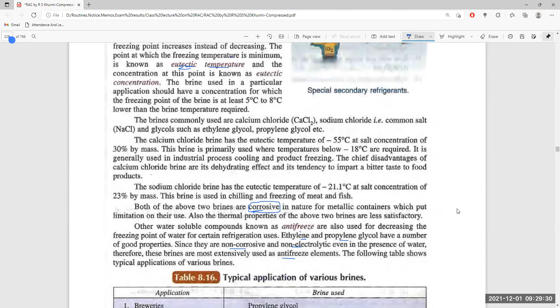Other water soluble compounds known as antifreeze are also used for decreasing the freezing point of water for certain refrigeration use. Ethylene and propylene glycol have a number of good properties since they are non-corrosive and non-electrolytic even in the presence of water. Therefore, these brines are most extensively used as antifreeze solutions. So first we have salt water used as a secondary solution, then other water soluble compounds, antifreeze compounds, are also used for decreasing the freezing point of water, without any corrosive effect like brine solution.